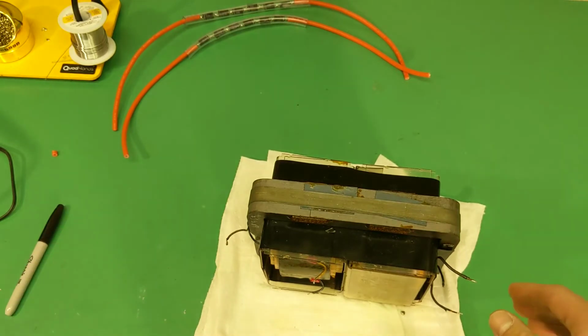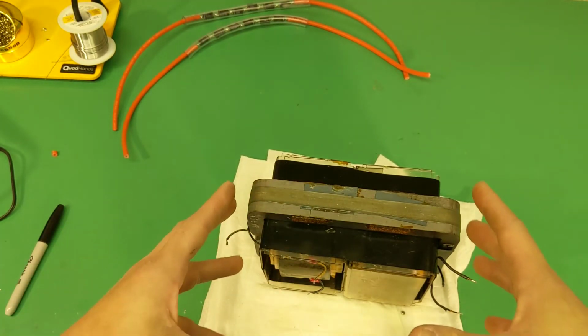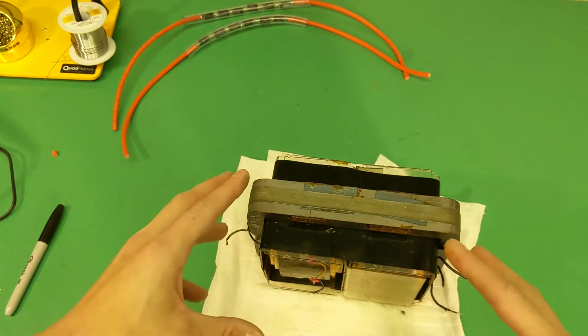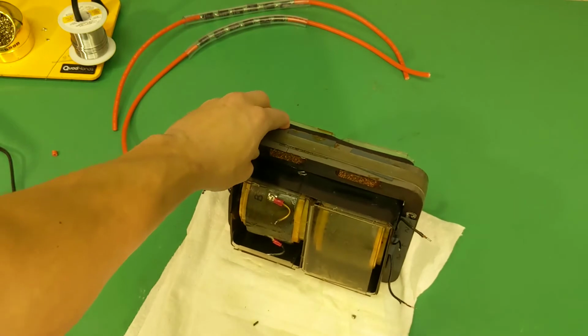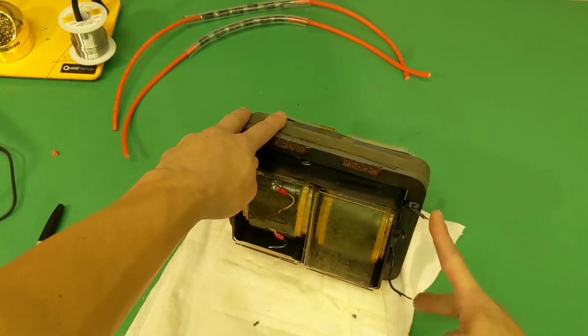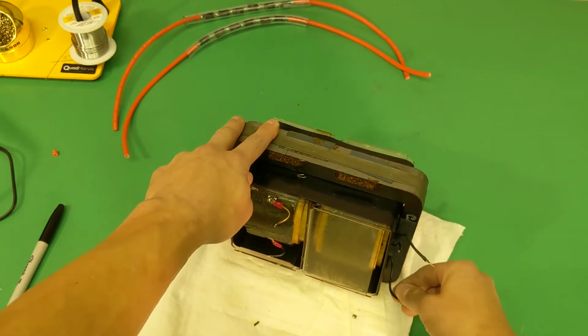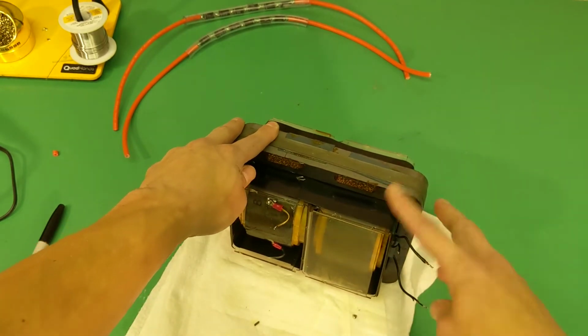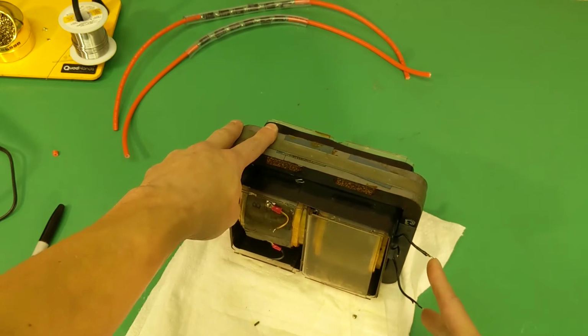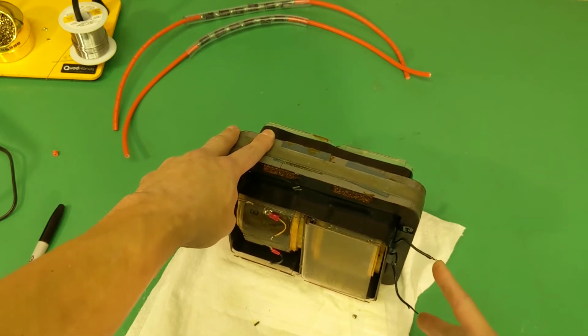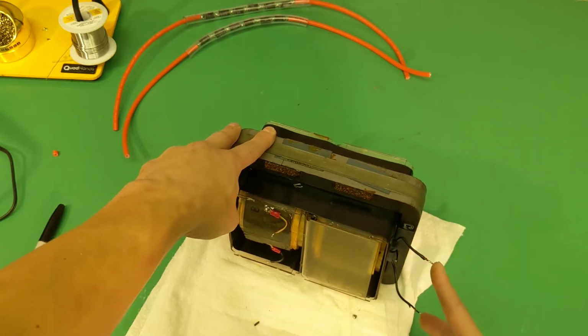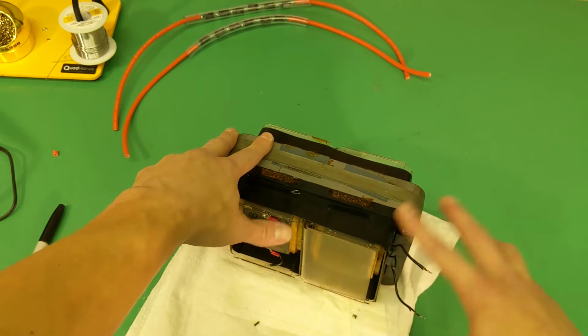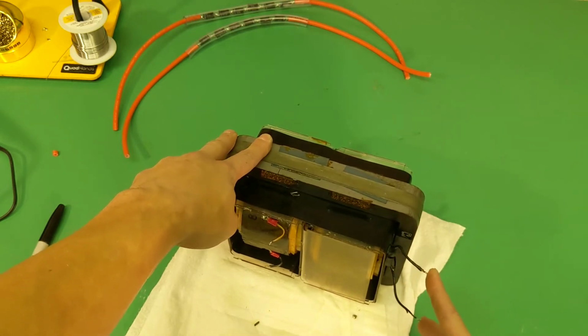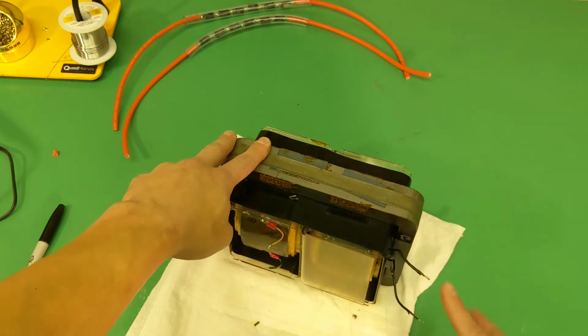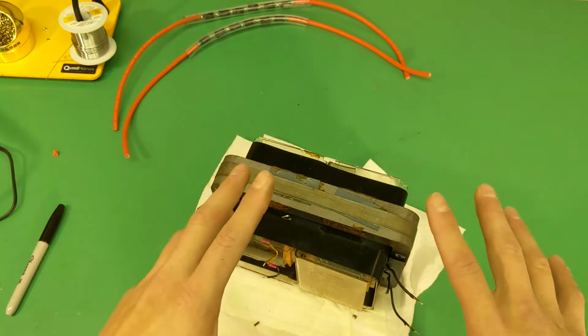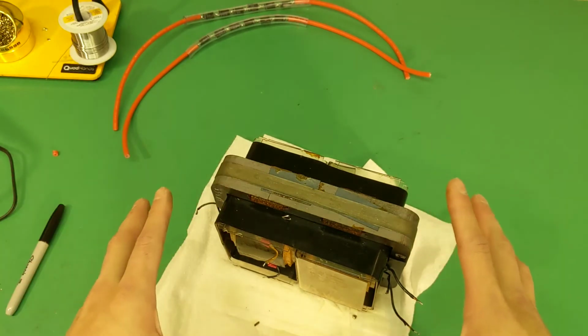To do that, we start by measuring the resistance of all the windings. I did a little cheat first: I already know these 2 thick wires coming out at the base are my primary coil, because I checked with a multimeter and found very low resistance, a couple ohms, and they're the thickest wires and not connected to anything else. So I know these 2 wires are most likely our primary coil - that's the only thing I know. The other 7 connections we have to map out to figure out the internal structure.